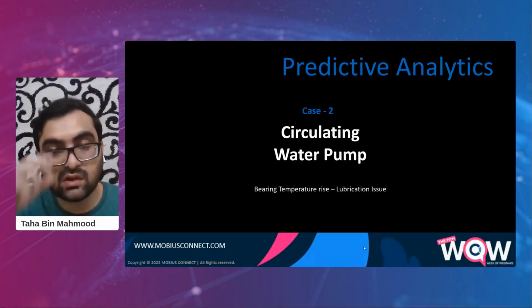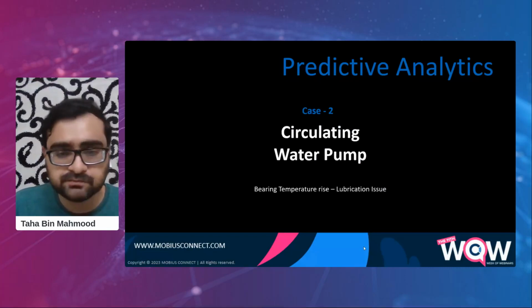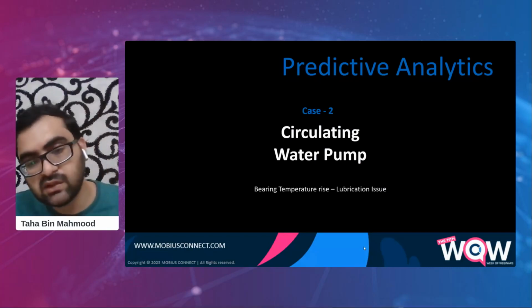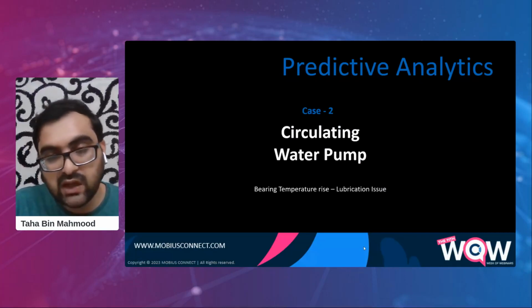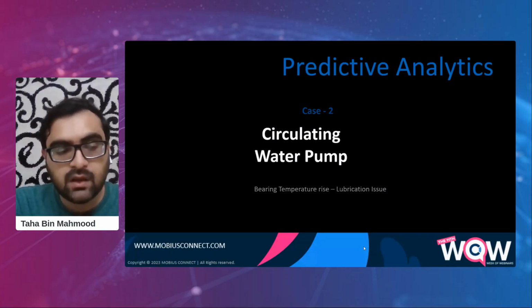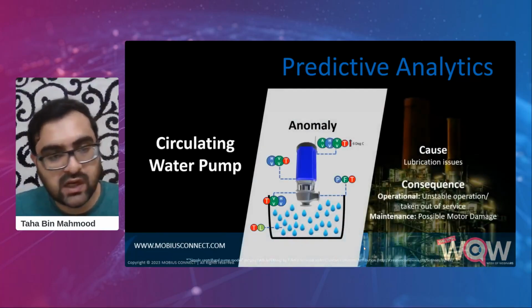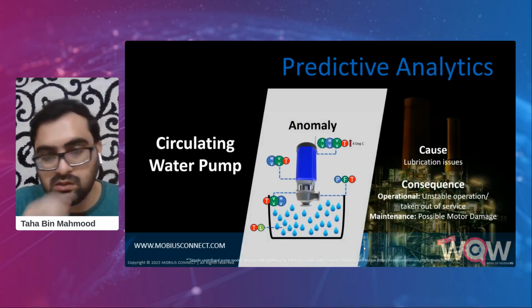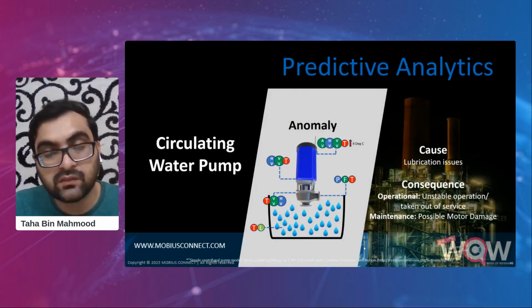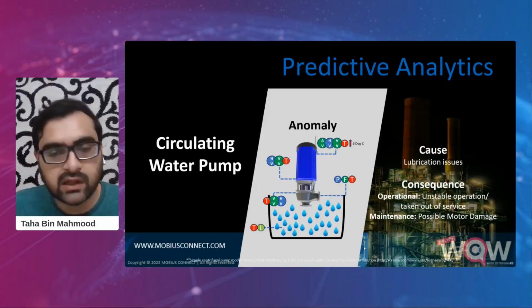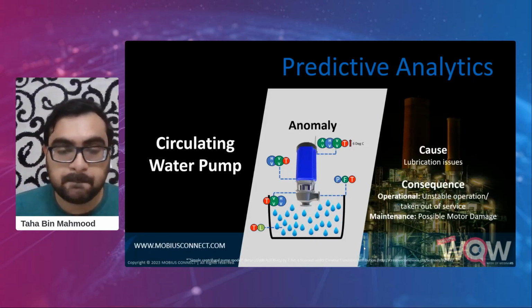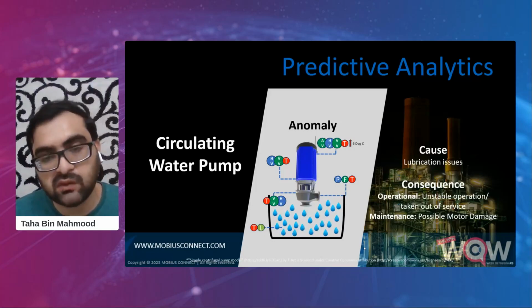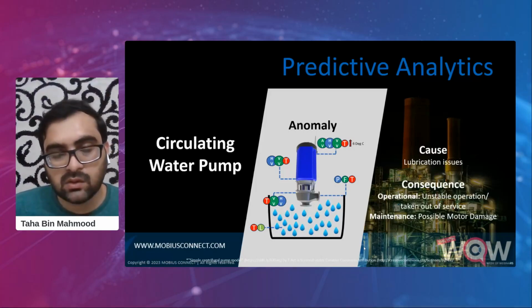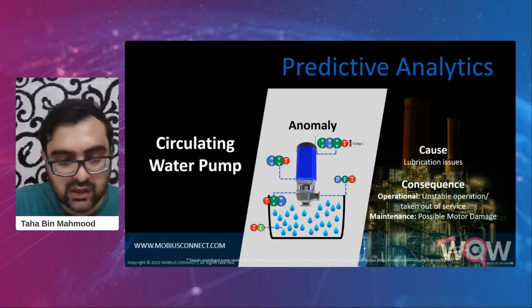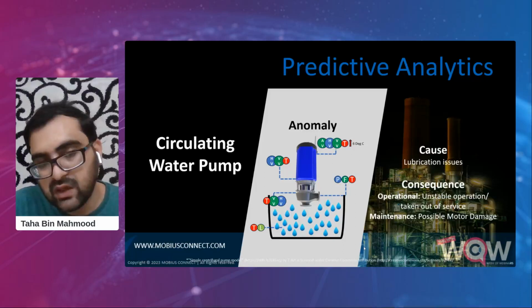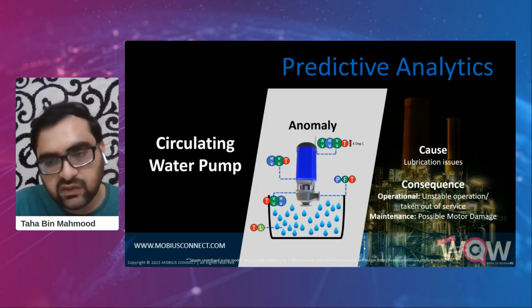The second is related to the cooling circulating water pump, where again a bearing temperature rise was noted, this time due to a lubrication issue. So what happened was that we had a circulating water pump where we saw a temperature rise of 6 degrees at the motor non-drive end bearing metal temperature, and no significant change was observed at other points of the bearing. So we deduced that it may be a lubrication issue. We vetted it and verified it with oil analysis as well.